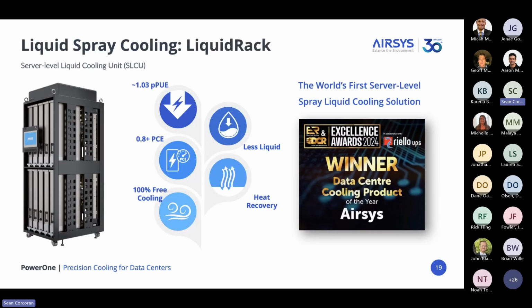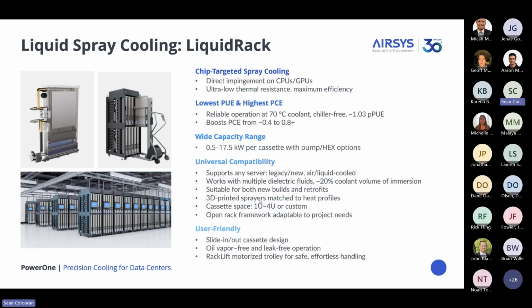And then we have our liquid spray cooling liquid rack, which is a cassette-based product. As you can see here, this is a cold plate where we utilize a spray. So it's a direct impingement with a spray directly onto the GPU, where the dielectric liquid then falls into a reservoir that is pumped back in. And there's a hot water, cold water, obviously, on a separate loop that removes the heat, and thus giving you higher kW per cassette. So these are actually 2Us, anywhere from 0.5 to 17.5 kW per cassette, which will achieve about 175 to 180 kW removal for this liquid rack.